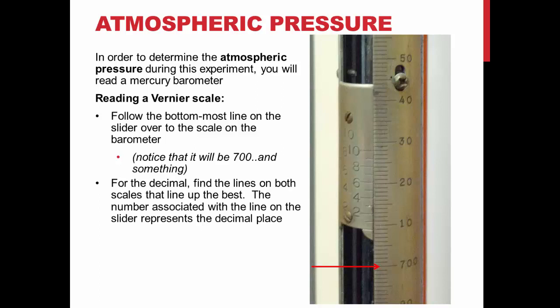This scale can be read to one decimal place, which can be found by looking to see which gradations on the right-hand scale line up best with the ones on the left-hand scale. In the picture, you can see that only the gradations for 0.9 line up with those on the right-hand side. This means your decimal place is 0.9, giving you an overall reading of 708.9 mmHg.